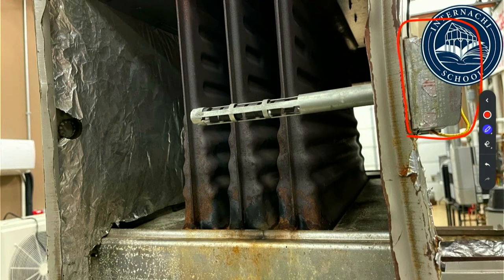I know a lot of people that belong to this group are still taking their home inspector exam. And that's like one of the questions on these older things: what temperature did it turn it on? What temperature did it turn it off? What temperature did it shut down? And it's going to be whatever the data plate says is the right answer. But it's usually going to be the middle number. It turns the fan on. The lowest number turns the fan off. And the highest number is going to shut it down, over limit. Yeah, so usually it's going to be like 100, 140, and 200, somewhere in that ballpark. Yeah. Usually 200 is the upper limit. Exactly, and that's when the whole furnace shuts down.